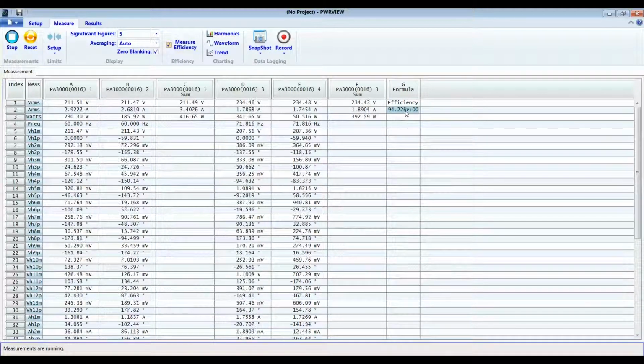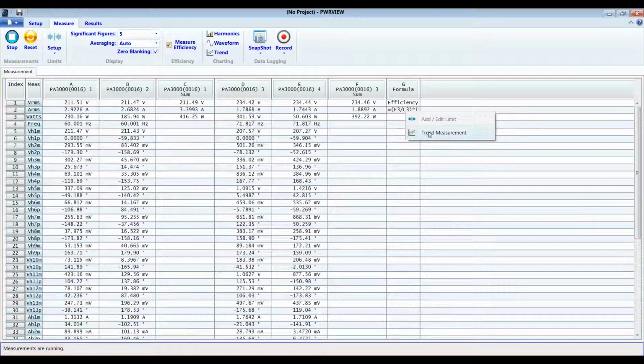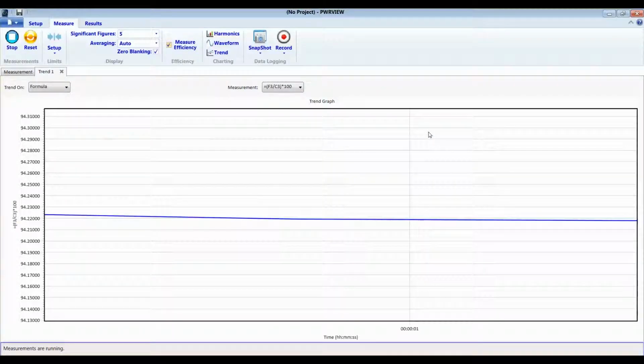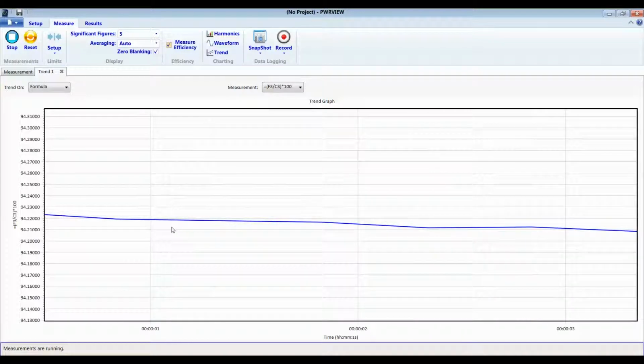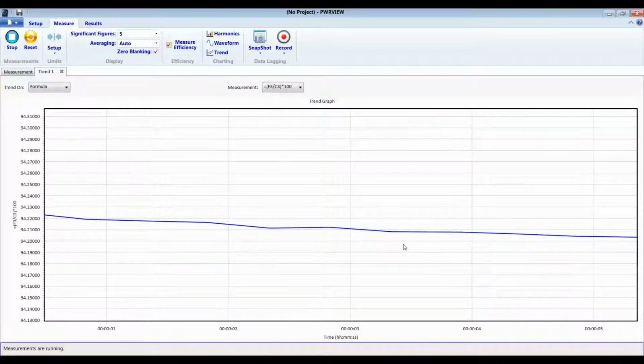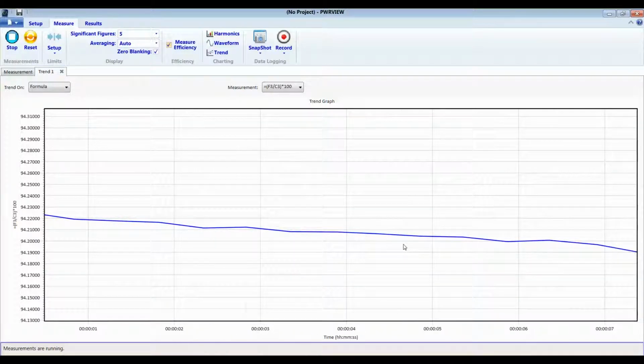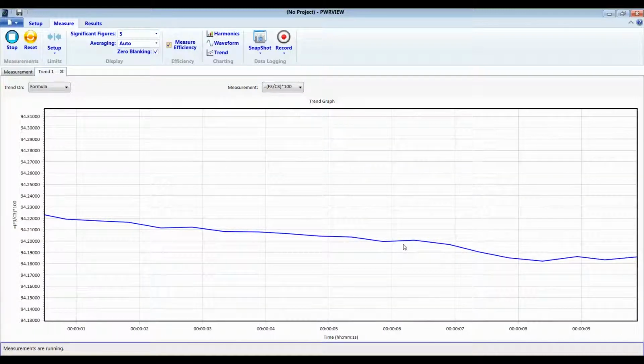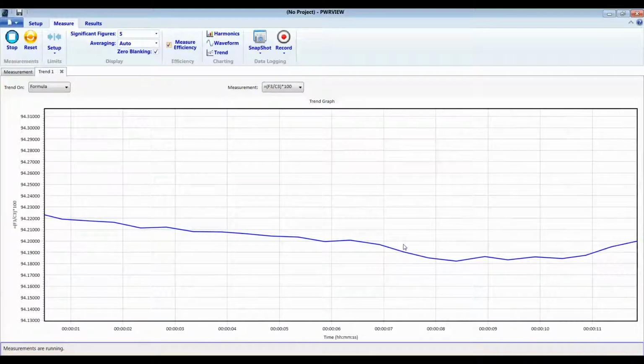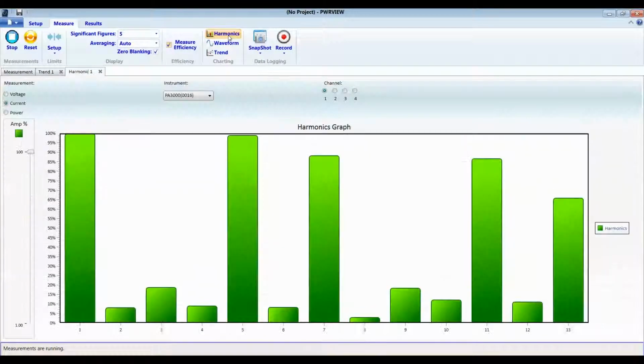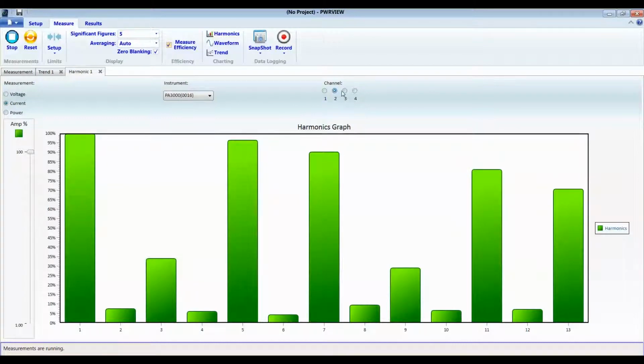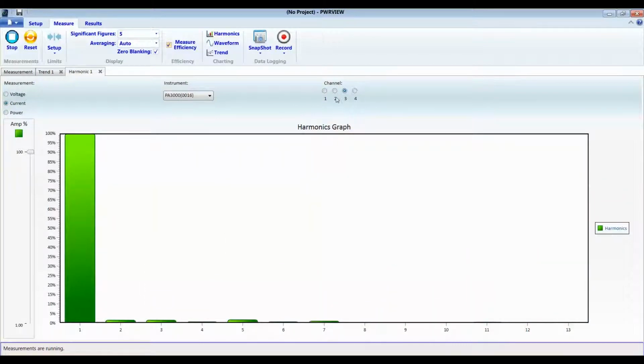To monitor efficiency over load changes, we can trend the efficiency by right clicking on this cell right here, right? So there you go. You can see how the efficiency trends over time. You can change the load if you want to see how it changes with load, right? We'll keep it constant. We can also look at the harmonics. So we can click on the harmonics button right here, which will give you harmonics on all the channels, right? And you can switch between channels if you want, right? There you have it. That's how you test efficiency on a 3-phase motor drive system.